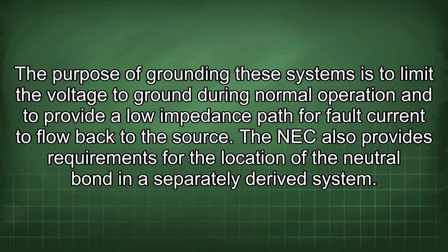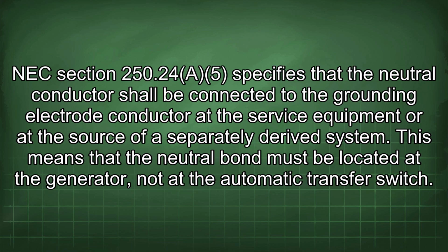The NEC also provides requirements for the location of the neutral bond in a separately derived system. NEC Section 250.24 specifies that the neutral conductor shall be connected to the grounding electrode conductor at the service equipment or at the source of a separately derived system.